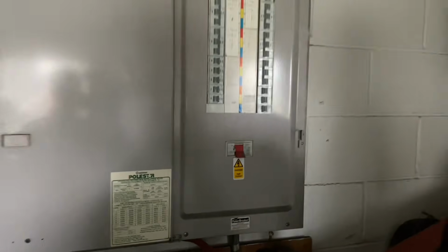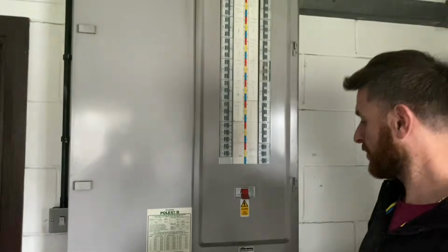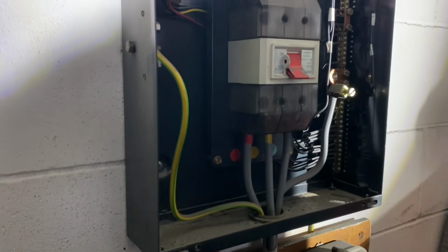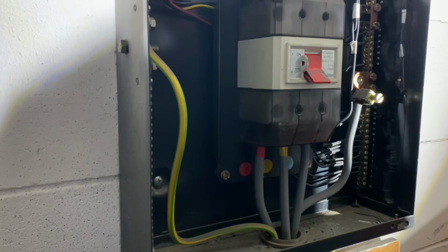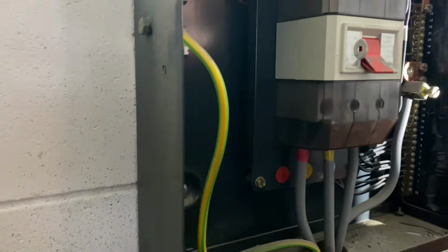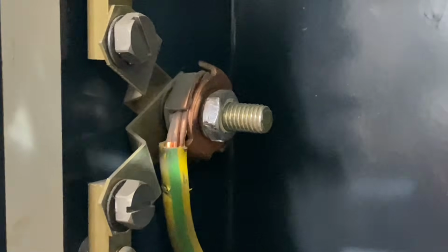Okay, so we're going to get the cover off and look at doing these tests Matt described at the start of the video. So the board's off, the cover's off, and we're now going to carry out the external earth fault loop impedance test. Just remind me why I'm going to disconnect the earthing conductor, which is here. Yes, it is the main earthing conductor.